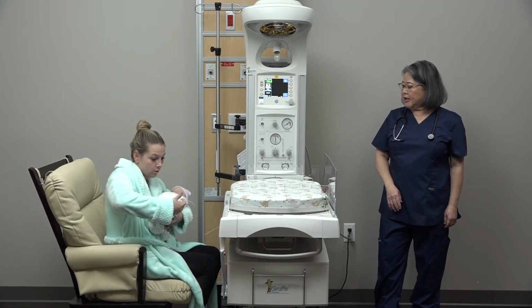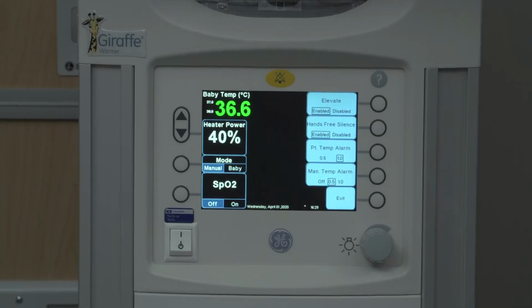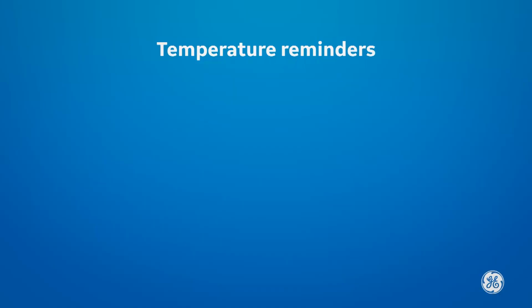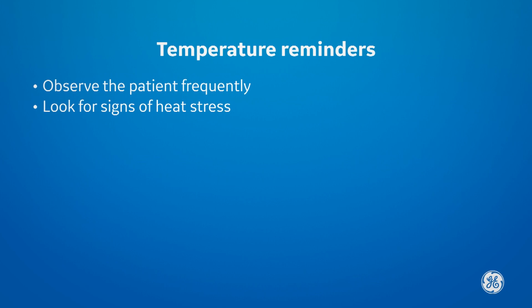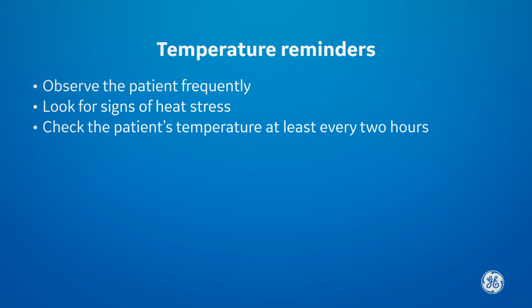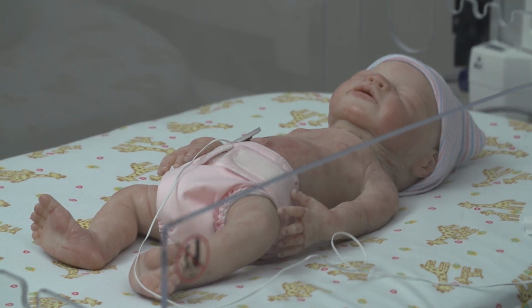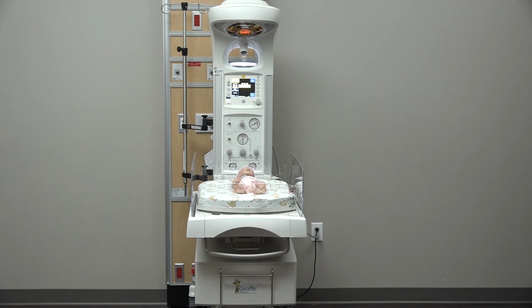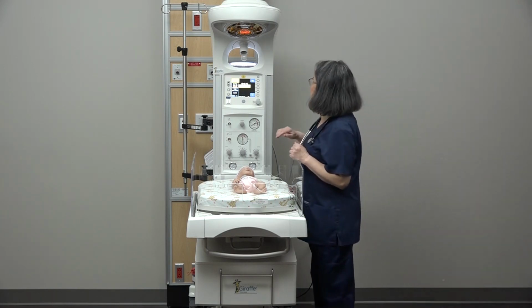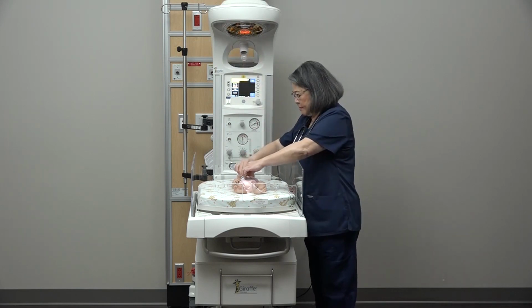Temperature control is important and should be monitored and maintained closely. Adjust baby mode temperature as necessary to get the correct temperature at the remote measurement site, such as the axilla or rectum. Here are some reminders for optimal temperature monitoring. Observe the patient frequently, looking for signs of heat stress, such as skin redness, warmth to touch, diaphoresis, or increased heart rate. Check the patient's temperature at least every 2 hours with an independent temperature measurement at a remote site, such as the axilla or rectum.